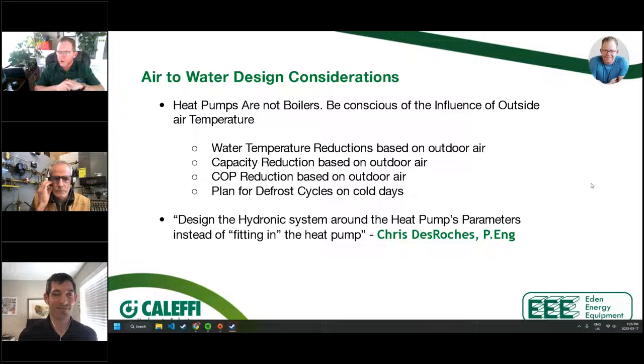We have to be very conscious of the things that are going to impact that unit. Those of you doing air source heat pumps already know this, that we have to be conscious of the outdoor temperature. So with an air to water unit, we have to be aware that as that outdoor temperature increases or decreases, it's impacting multiple things. Specifically, it's impacting the overall capacity of that unit, depending on what the outdoor air temperature is. It's also impacting the capabilities of that unit and what it can produce from a water temperature standpoint.